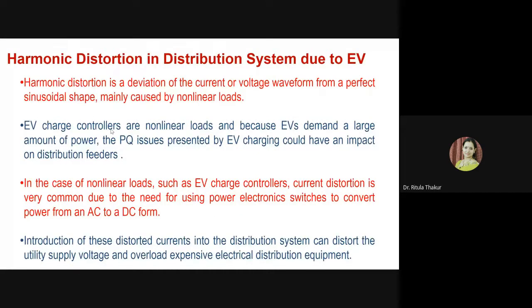We know that harmonic distortion is a deviation of the current or voltage waveform from a perfect sinusoidal shape, mainly caused by nonlinear loads. And our EV charging stations are nonlinear because of the power electronic components in them. Because EVs demand a large amount of power, the power quality issues presented by EV charging could have an impact on the distribution feeders. In the case of nonlinear loads like EV charge controllers, current distortion is very common due to the use of power electronic switches to convert power from AC to DC form. When we talk about EV charge controllers, I think you must know that we mainly have three types: type 1, type 2, and DC fast charging controllers.